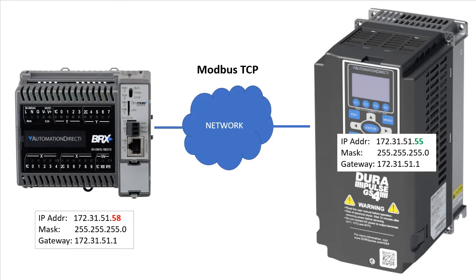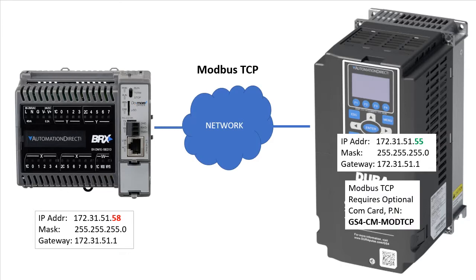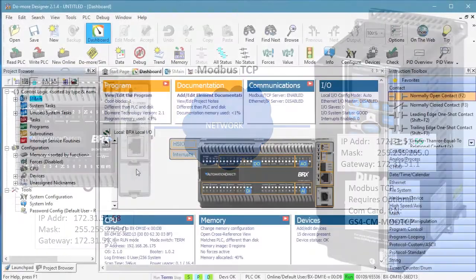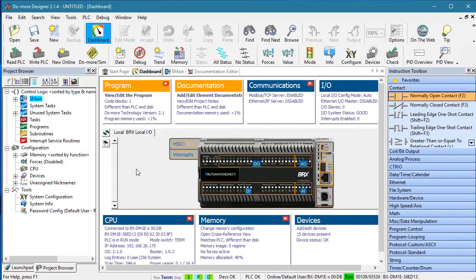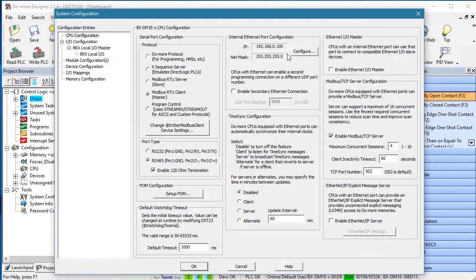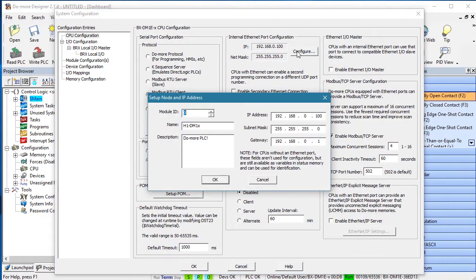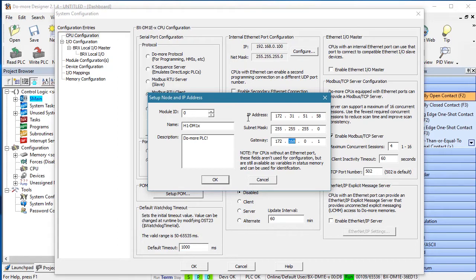You'll also need the GS4 Drive's optional Modbus TCP com card to communicate using Modbus TCP. To configure a DoMore enabled PLC for Modbus TCP, you just go to the system configuration and set up the IP address to be compatible with the network the GS4 Drive is on, which in this example is this.